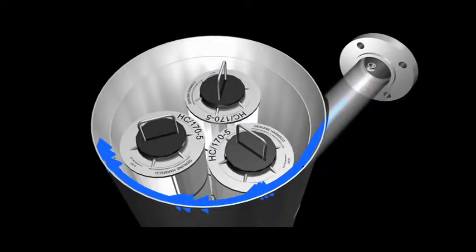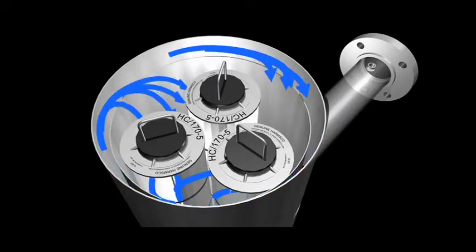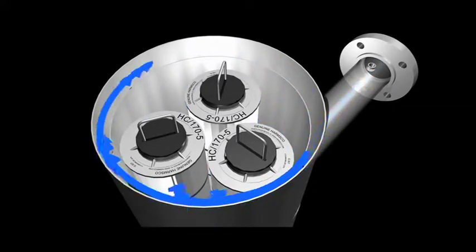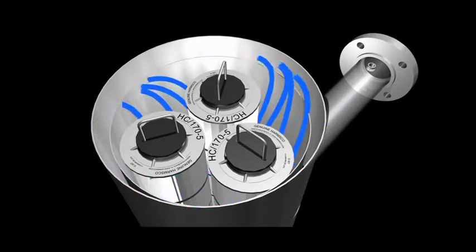After dropping dense solids into the outer chamber of the housing, the liquid flows over the inner wall and into the filter chamber. The cyclonic effect of the flow continues into this chamber, and it further loses velocity as liquid flows around the filter cartridges. This creates a very even loading of the cartridges and further extends cartridge life.